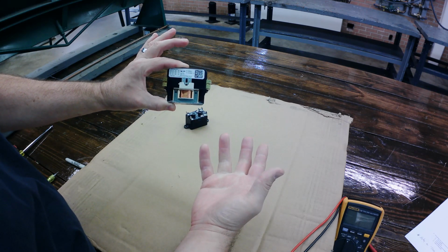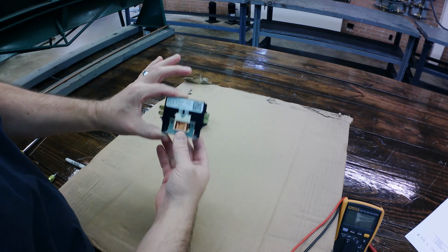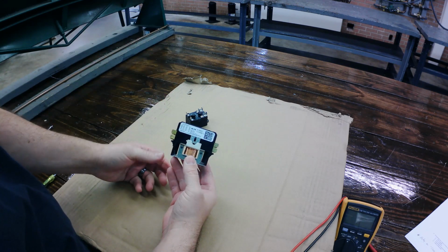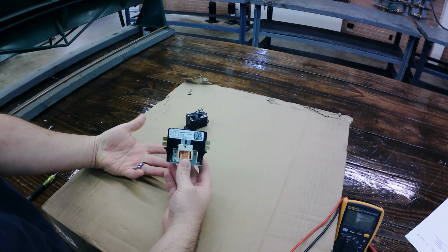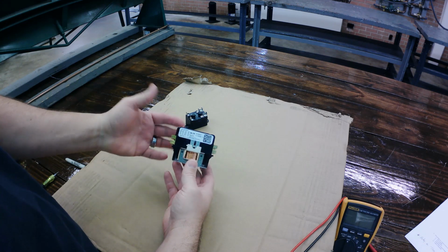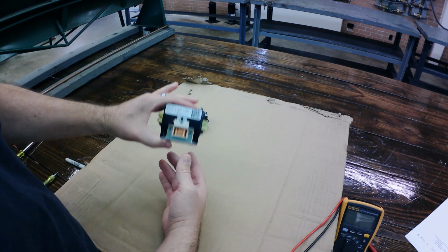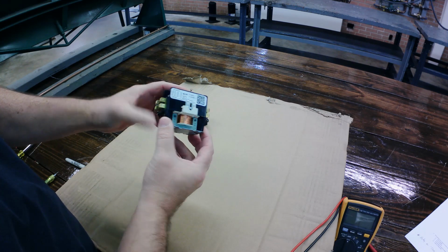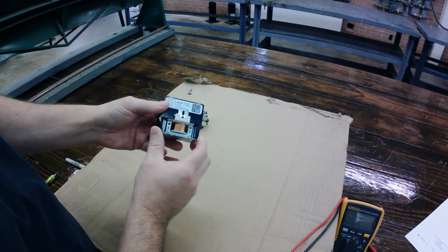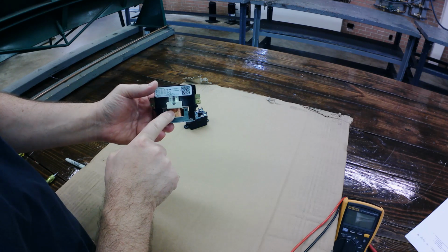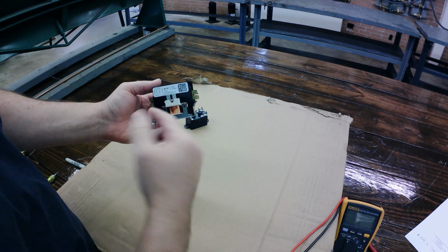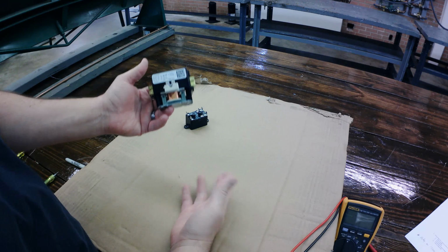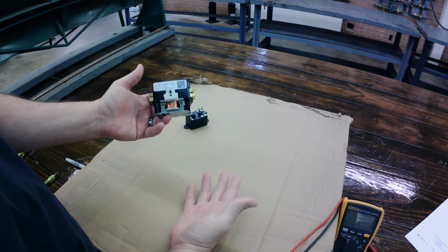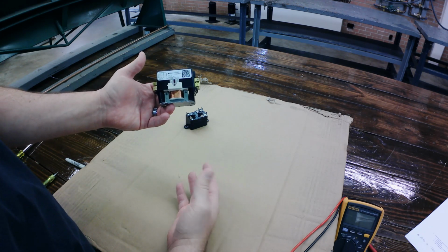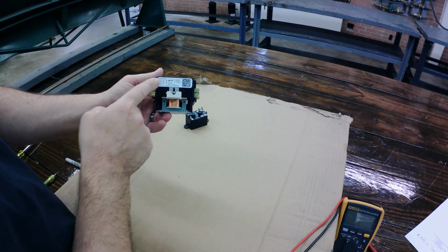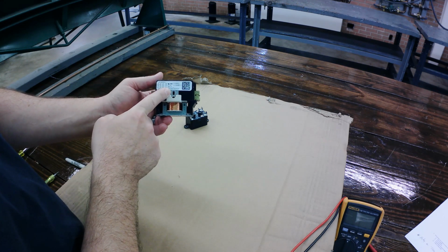And this is more so residential stuff, right? There are contactors that have 120 volt coils, or a 208, 240 coil, or even a 460 in some rooftop package units on the commercial side. But speaking just for residential stuff, a real simple contactor is generally 24 volts, and that coil is controlled by the thermostat. And it may or may not have some low pressure switches or high pressure switches or some type of safety wired in series with that circuit. But generally on a contactor, the Y circuit ultimately ends at the contactor coil.